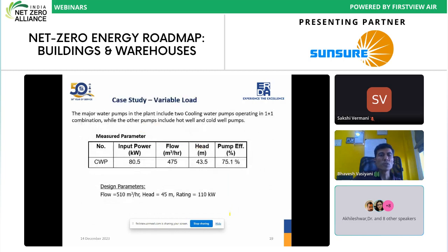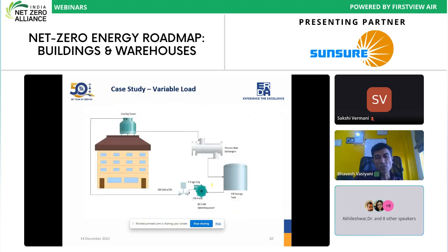Similarly, in case of variable load, where you are supplying to unoccupied areas, sometimes in a location your building or your warehouses are partially occupied or unoccupied. Based on that, you have some arrangement. In this case, the cooling water pump is supplying to the cooling tower at the top of the building, and again that cold water is coming, giving its cooling effect to various condensers and heat exchangers and stored in the storage tank. Now this cooling water pump is operating, and the discharge valve of this pump is operating as per the level of this storage tank.